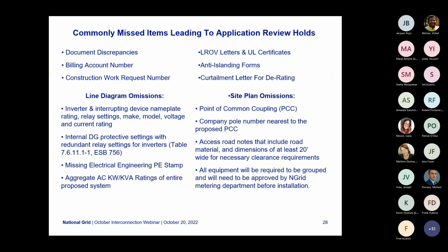This outlines some of the most commonly missing items that lead to application holds. A lot of them are document discrepancies between either the legal information form or the application form, where the information isn't correct on one of them, or some of the account numbers don't match up. Missing a construction work request number, which is required for almost every single case that requires any work, whether it's swapping a meter or new distribution system construction, anti-islanding forms, curtailment letter for derating. Some of the things that get line diagrams put on hold are the internal DG protective settings that aren't labeled on the one line, missing an electrical PE stamp.